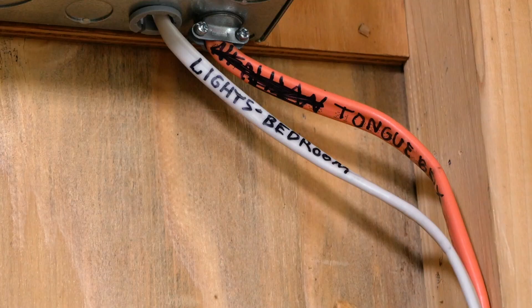Coming down here, this is the first of two small appliance circuits. These are both 20 amp circuits that come to the middle of the trailer and feed the kitchen counters. One circuit goes above the counters, one goes below, and this lets us split high loads like tea kettles, hot plates, or ovens so we can run a couple at once without tripping one of these breakers. You could also potentially pull a tankless or small tanked switchable hot water heater off one of these, or do a separate 20 amp circuit for that.